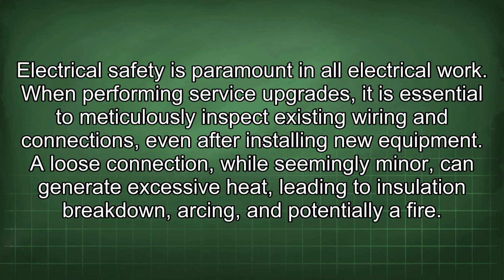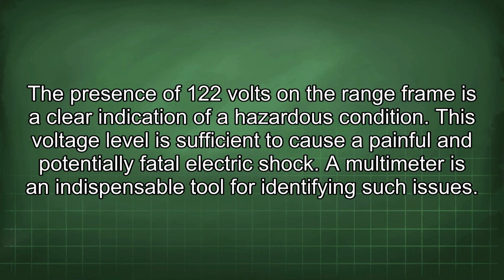When performing service upgrades, it is essential to meticulously inspect existing wiring and connections, even after installing new equipment. A loose connection, while seemingly minor, can generate excessive heat, leading to insulation breakdown, arcing, and potentially a fire. The presence of 122 volts on the range frame is a clear indication of a hazardous condition. This voltage level is sufficient to cause a painful and potentially fatal electric shock.